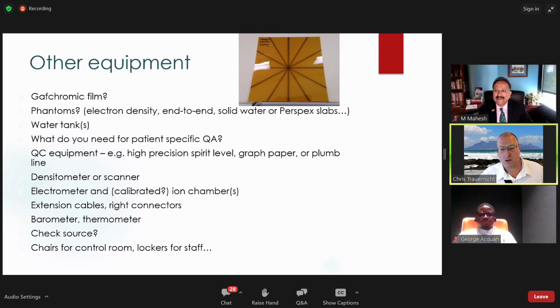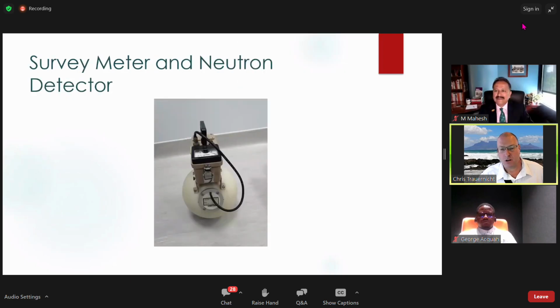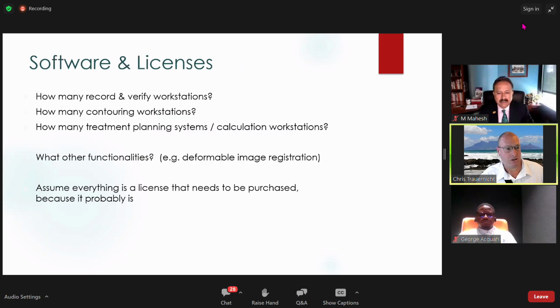Think about a survey meter and neutron detector. If you don't have one, before acceptance testing starts, you want to check the safety and security of the premises. You will need a calibrated survey meter and potentially a neutron detector. Just something to bear in mind. Of course, we've got to look at software and licenses as well. How many record and verify workstations, how many contouring workstations, how many calculation workstations, what other functionalities do you want?